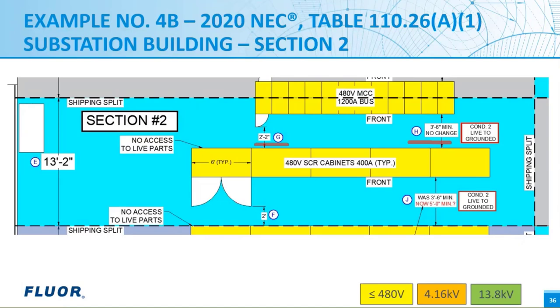Now let's look at the dimensions near bubble F and J. Near bubble J, the 2017 NEC only required 3 foot 6 inches of clearance between the front of the SCR cabinets and the rear of the cabinets that are in the building section right below it.